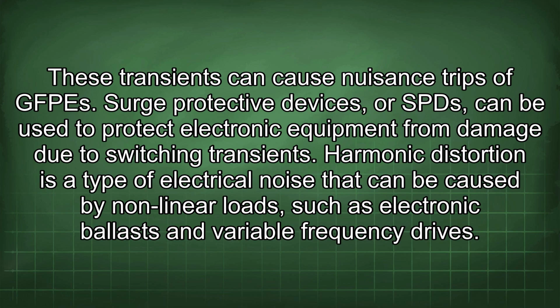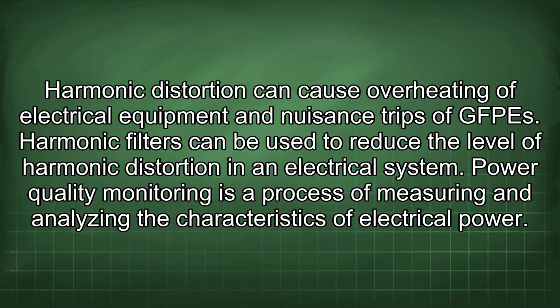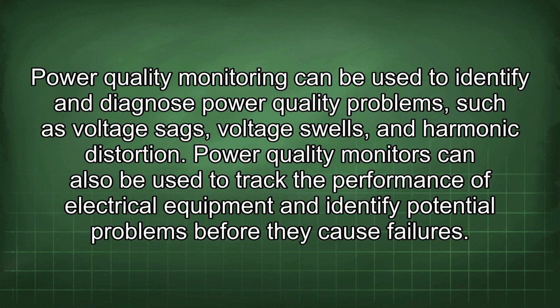Harmonic distortion is a type of electrical noise that can be caused by nonlinear loads such as electronic ballasts and variable frequency drives. Harmonic distortion can cause overheating of electrical equipment and nuisance trips of GFPEs. Harmonic filters can be used to reduce the level of harmonic distortion in an electrical system. Power quality monitoring is a process of measuring and analyzing the characteristics of electrical power. Power quality monitoring can be used to identify and diagnose power quality problems such as voltage sags, voltage swells, and harmonic distortion.